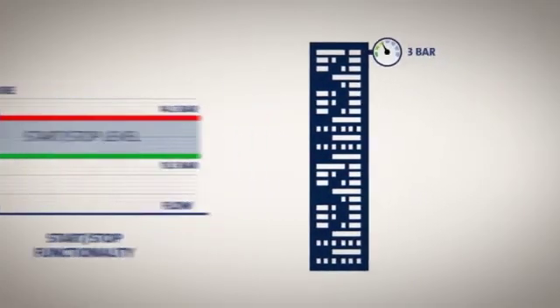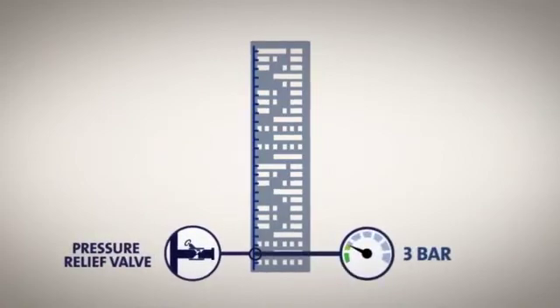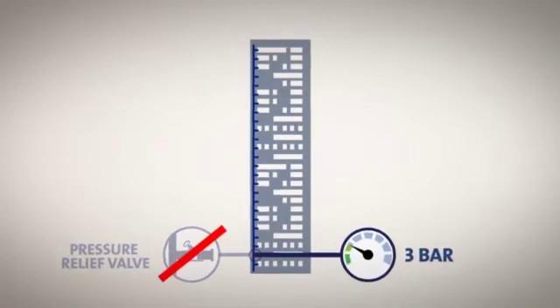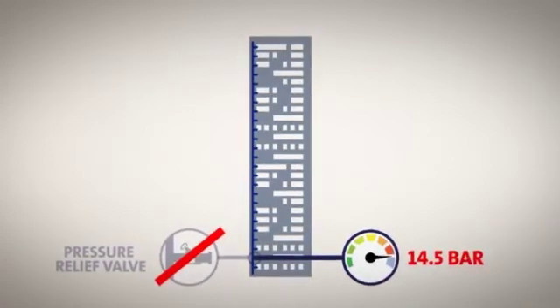To reduce the pressure on the lower floors, pressure relief valves must be fitted on the riser pipe. Otherwise, the pressure on the ground floor will be equal to the stop level, in this case 14.5 bar, which is far too high. In buildings that are maximum 50 meters high, pressure relief valves may not be necessary.